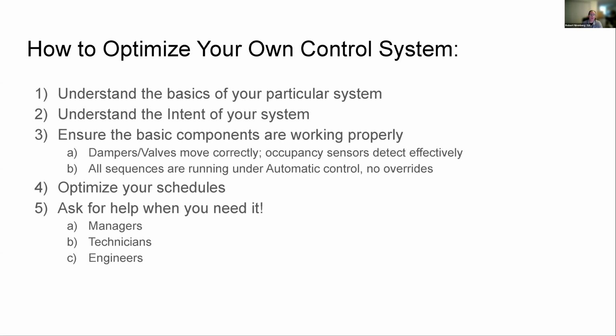If you're using the $5 sensor you got off Amazon to calibrate your building control sensors, I'm not saying it's a bad sensor, but look at its calibration sheet and make sure it's reliable. Also, make sure your sequences are running in automatic control. Overrides are a very useful tool in the short term, but in the long term they are very parasitic for the function and efficiency of our systems.